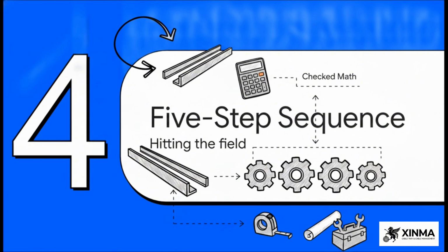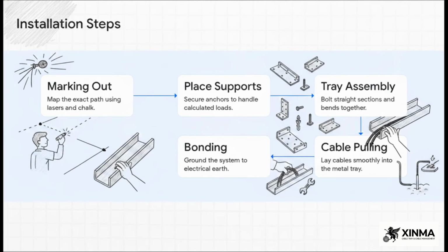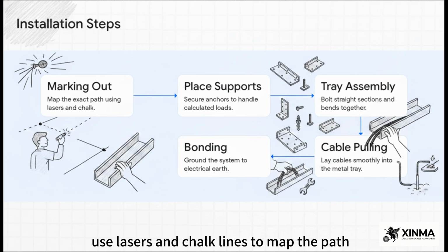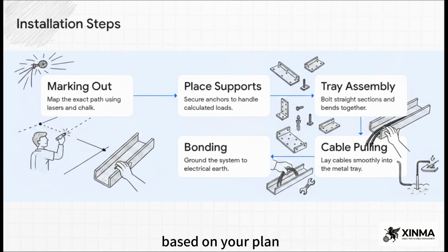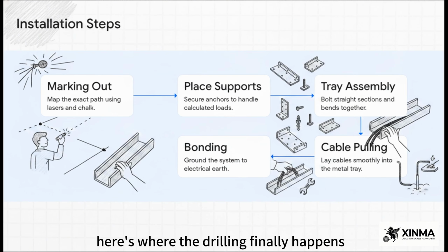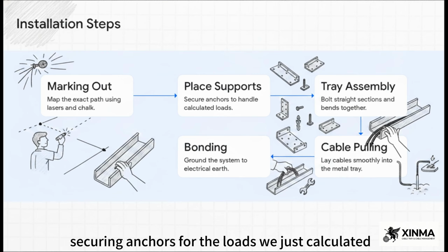Section 4. 5-step site installation sequence. Hitting the field. So, the route is perfectly planned, the math is triple-checked, now we execute. Following this exact sequence is how you translate that perfect blueprint into the real world. Step 1. Marking out the route. Use lasers and chalk lines to map the path on the ceiling based on your plan. Step 2. Placing supports and brackets. Here's where the drilling finally happens, securing anchors for the loads we just calculated.